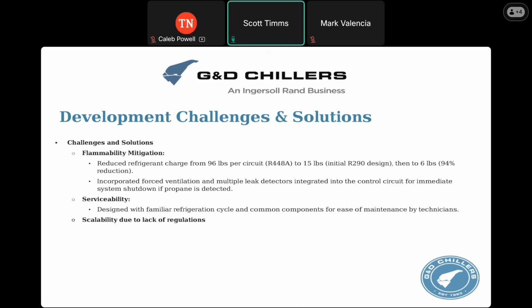So the other thing that we did there is we separated. So in your chillers that you folks have at your facilities now, you probably have a refrigeration and glycol system that's kind of intermingled with each other. And this one, we separated the propane system or the refrigeration system from the water system or the glycol system. And then we put in a C1D1, so it's explosion proof fan in the refrigeration side that keeps the refrigeration cabinet at negative pressure. So essentially, if there is a leak, the only place for the propane to go is through that fan and out through some ducting to a safe space, right? And then we have a leak detector there so that if it ever gets even close to the flammability limit, it's going to pull power from the entire unit.